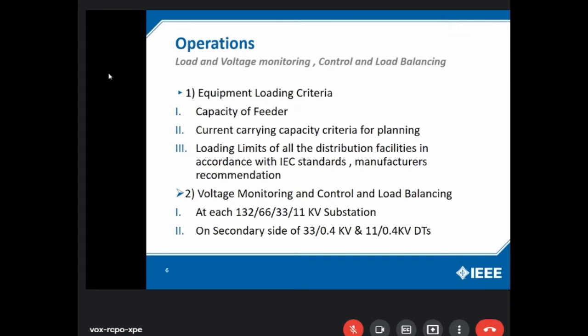In continuation, we see how the load and the voltage monitoring, control, and the load balancing is carried out by the distribution companies. This is the guideline for the distribution companies. Number one, equipment loading criteria. Capacity of the feeder, standard capacity of the feeder, current carrying capacity, criteria for the planning. Of course, the feeder can carry load up to 300 amps, 400 amps, but while planning, you plan for 60% of the loading or 70% of the loading. This is what we have discussed in the planning subcode of the distribution code.